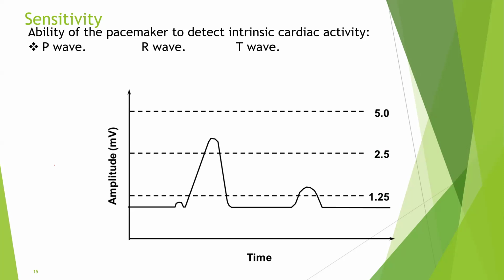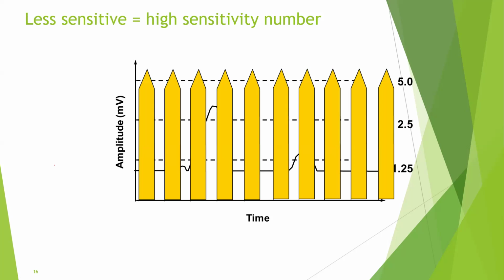So how is the depolarization or repolarization of the atrium and the ventricle sensed? Normally the device has a mechanism to sense intrinsic activity, and it is programmable. You can program it to a low number or a high number. The lower the number is, the more sensitive, and the higher the number is, the less sensitive. So it is reversed. If you program the sensitivity to 5, for example, the device will not be able to see any of the complex. It will not see the P wave, it will not see the QRS, it will not see the T wave. So the number is high, but the sensitivity is low.